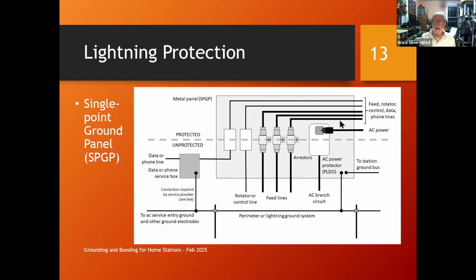You want to keep those cables away from the cables that go into your station. It looks nicer if you bundle everything together and lace it up or use tie wraps, but the problem is lightning will jump from an unprotected cable to a protected one, defeating your arresters and grounding scheme. So have two bundles: one for protected stuff and one for unprotected stuff.